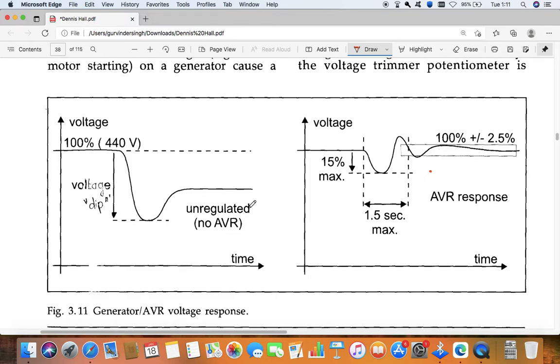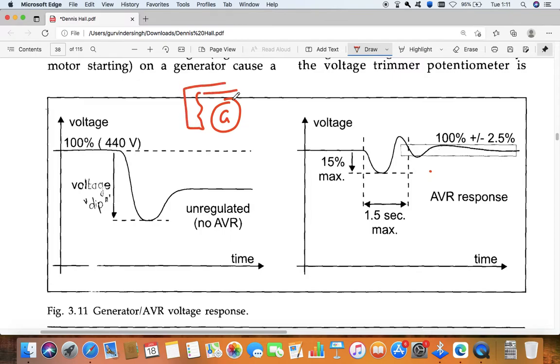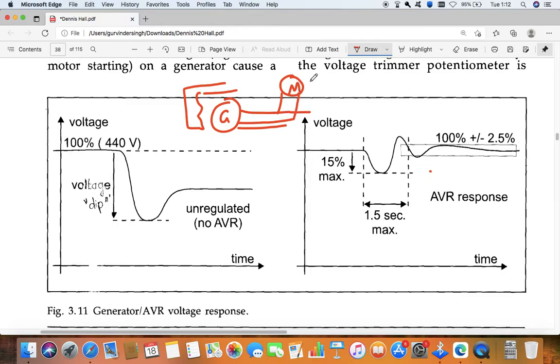So I will explain what actually happens. For example, we have a generator. The generator has a field winding and it is providing supply to various consumers - various motors and other things. When we connect one motor to the generator, the motor will draw a very high current and it will cause a voltage dip inside the winding of the generator.